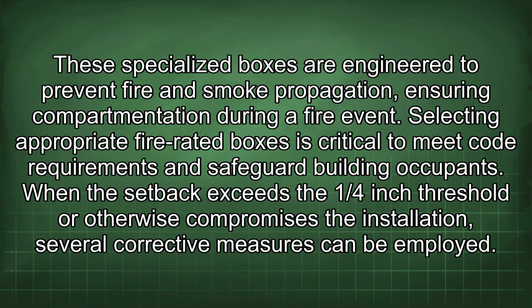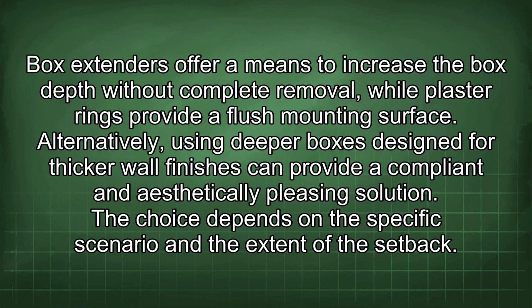When the setback exceeds the 1/4-inch threshold or otherwise compromises the installation, several corrective measures can be employed. Box extenders offer a means to increase the box depth without complete removal, while plaster rings provide a flush mounting surface. Alternatively, using deeper boxes designed for thicker wall finishes can provide a compliant and aesthetically pleasing solution. The choice depends on the specific scenario and the extent of the setback.